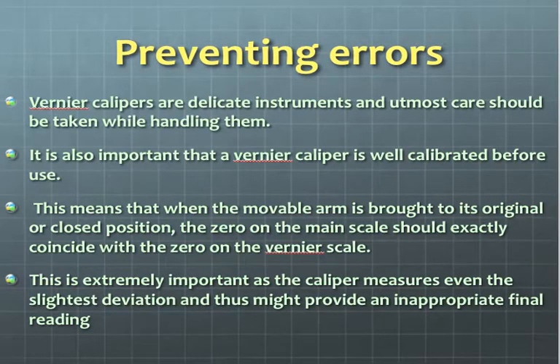This means that when the movable arm is brought to its original or closed position, the 0 on the main scale should exactly coincide with the 0 on the vernier scale. This is extremely important as the caliper measures even the slightest deviation and thus might provide an inappropriate final reading.